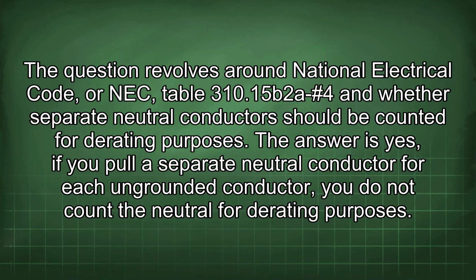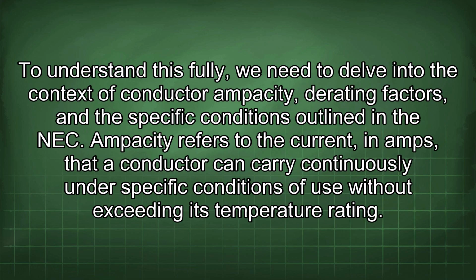The question revolves around National Electrical Code, or NEC, Table 310.15(B)(2)(a) #4 and whether separate neutral conductors should be counted for derating purposes. The answer is yes. If you pull a separate neutral conductor for each ungrounded conductor, you do not count the neutral for derating purposes.